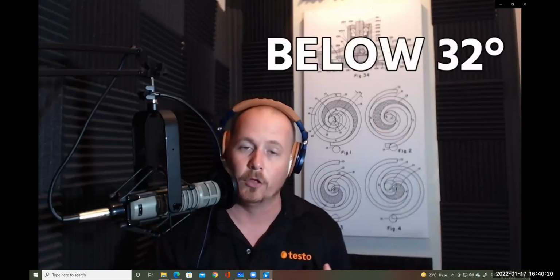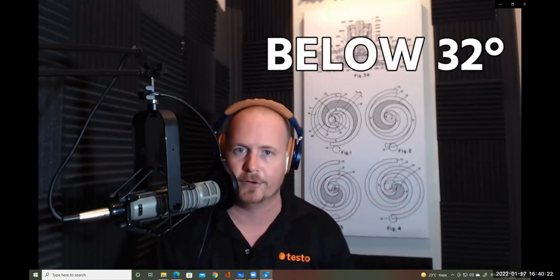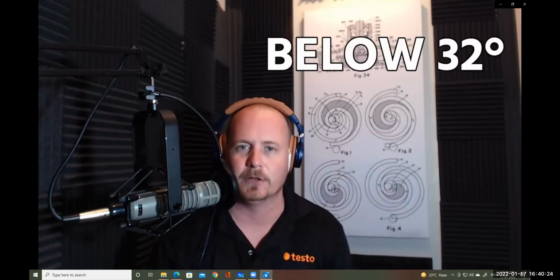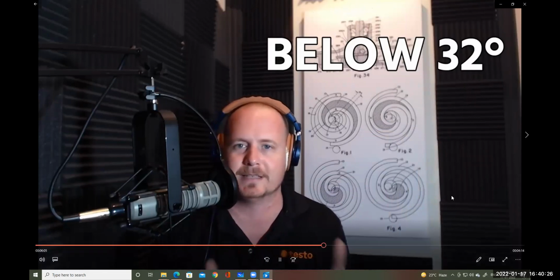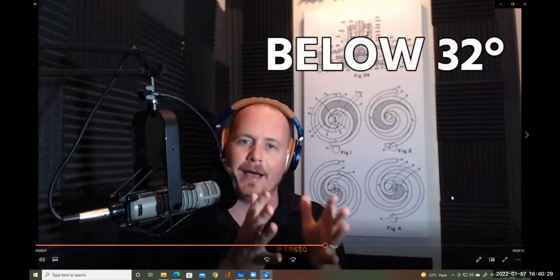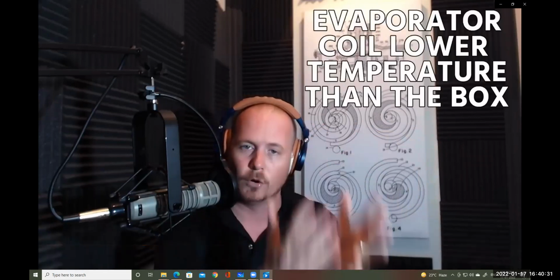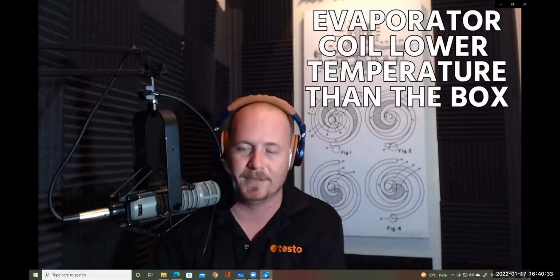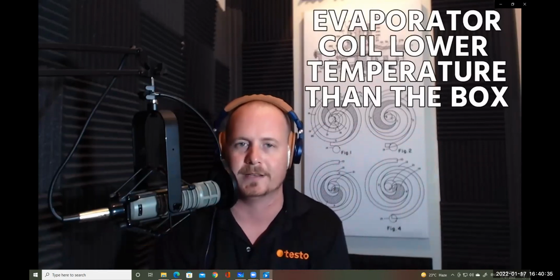Juxtapose that to, say, a freezer, where we obviously have to get that evaporator coil below 32 degrees. Otherwise, we would not get the product below 32. It wouldn't be a freezer unless it was below 32. In fact, a lot of freezers are minus 10, minus 20 degrees Fahrenheit. And so you have to have an evaporator coil that is lower than the desired temperature of the box or of the product inside the box.